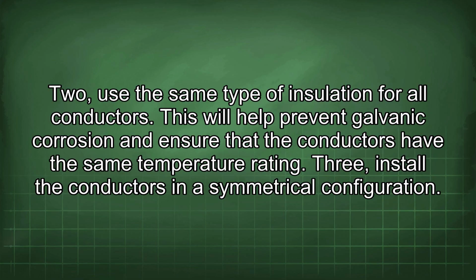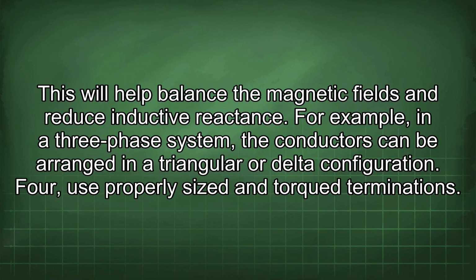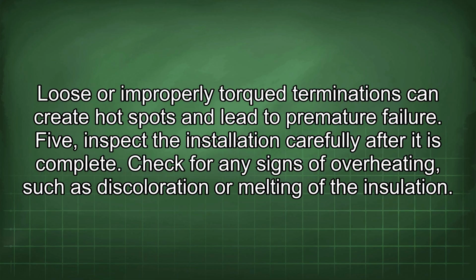3. Install the conductors in a symmetrical configuration. This will help balance the magnetic fields and reduce inductive reactance. For example, in a three-phase system, the conductors can be arranged in a triangular or delta configuration. 4. Use properly sized and torqued terminations. Loose or improperly torqued terminations can create hot spots and lead to premature failure.